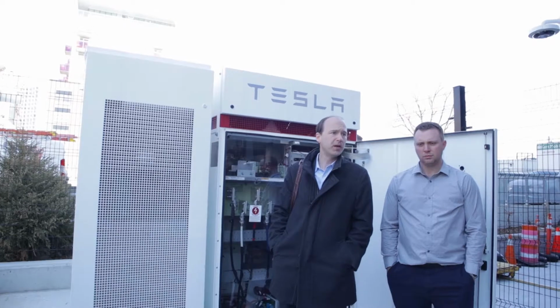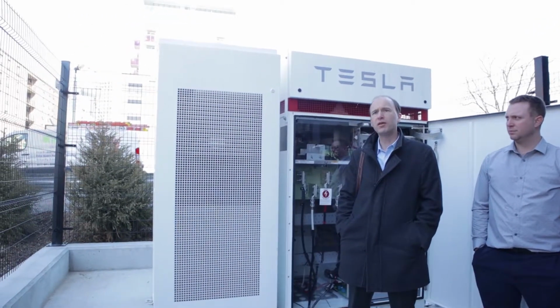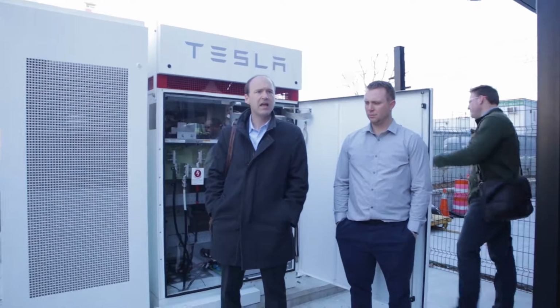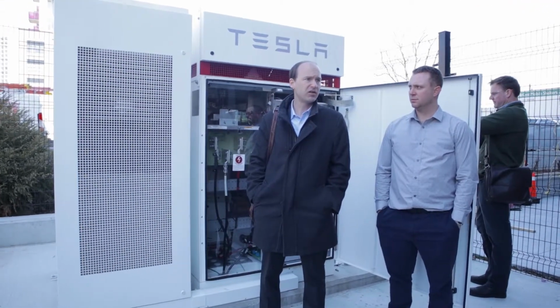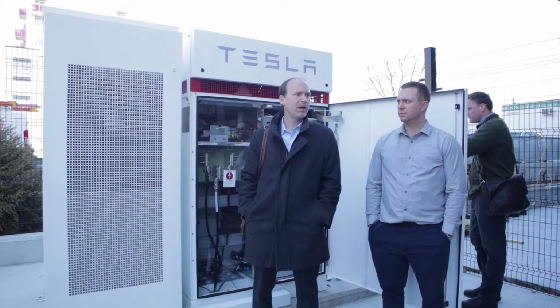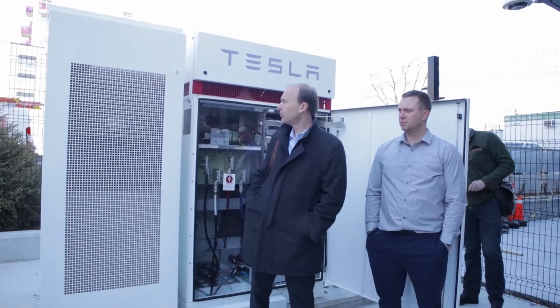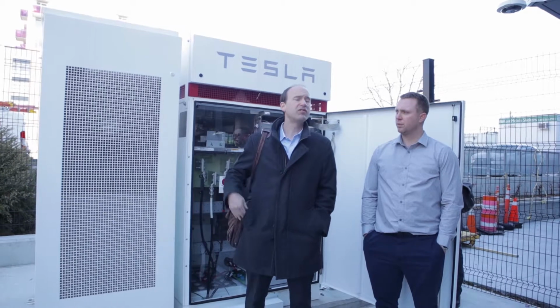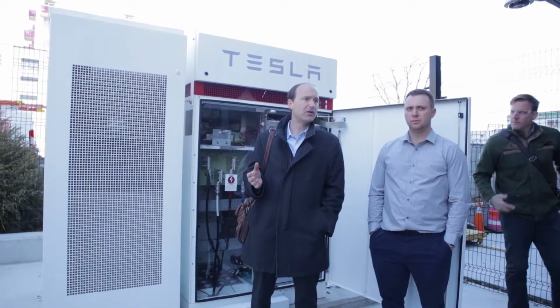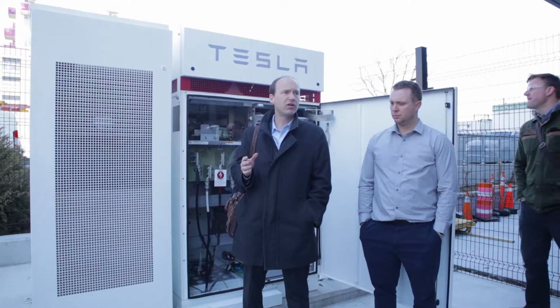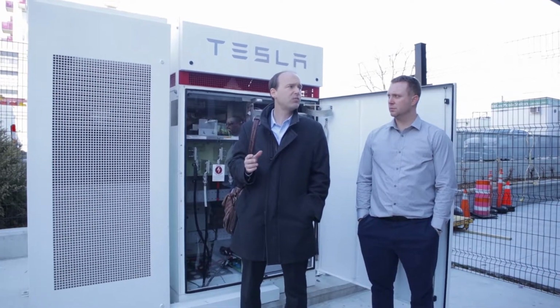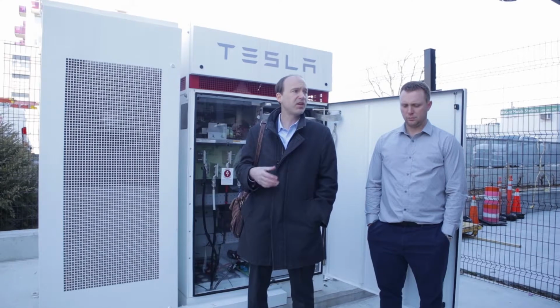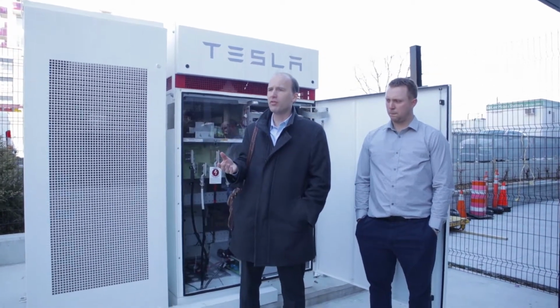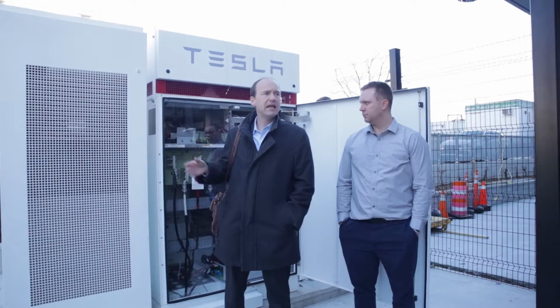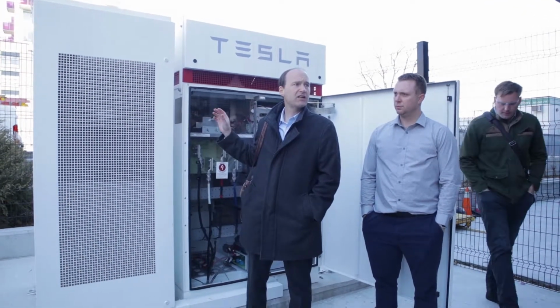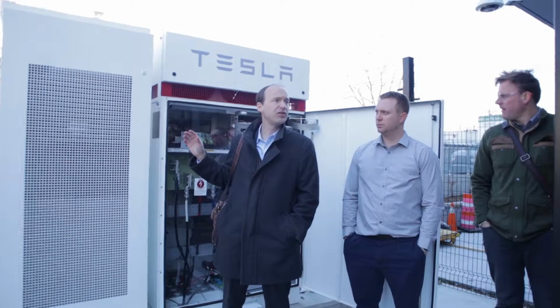But in terms of a commercial building of this size, the peak load here, as you'll see when we do the live display, is about 500 to 600 kilowatts peak, averaging maybe 300 to 400 kilowatts. So this 100 kilowatt system certainly can't island the building—that's not its objective. It's not here to serve as a reliability asset, like when people put batteries in their homes so that when the power goes out, the battery can serve their home. Here, in most commercial settings, the objective of the battery is to reduce their electricity bill.